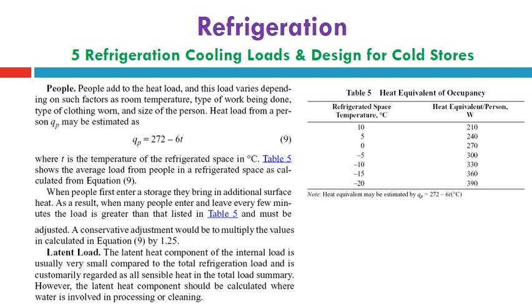Finally, when people first enter the storage, they bring additional surface heat. When many people enter and leave every few minutes, the load is greater than that listed in table 5 and must be adjusted. A conservative adjustment would be to multiply the values calculated in equation 9 by 1.25, to account for the movement of people in and out of the refrigerated space. Also, the latent heat component of the internal load is usually very small compared to the total refrigeration load and is customarily regarded as all sensible load in the total load summary. However, the latent heat component should be calculated where water is involved in processing or cleaning.